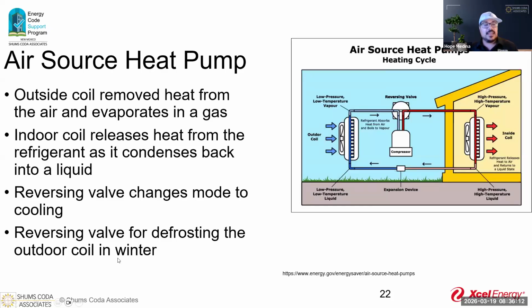So what that means is, the refrigerant can only operate along a certain temperature curve. If we go beyond that, oftentimes what we have to do is put this thing in a defrost mode. What that's going to mean is there might be some supplemental electric resistance heating or things like that that's going to pre-warm some of that coil so that the refrigerant can better do its job. So what it's going to take advantage of is the outside coil moving that air. Let me turn on my little, there it goes.